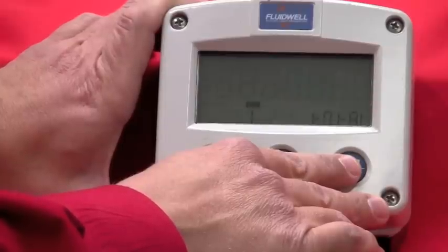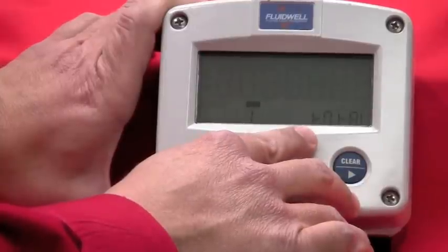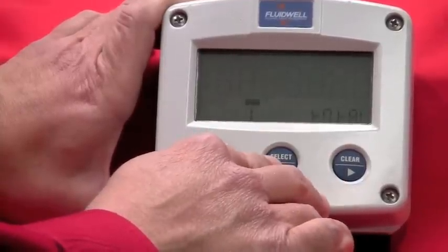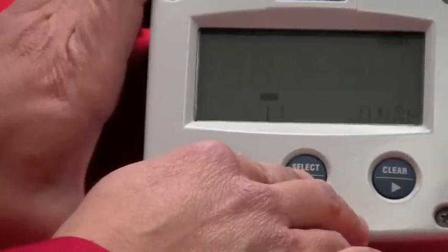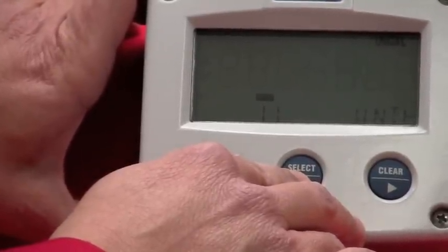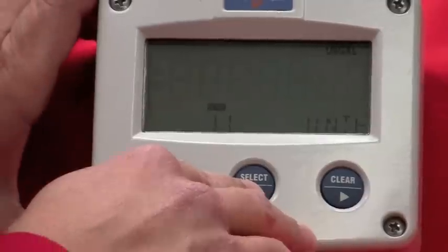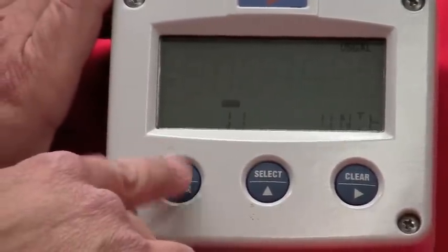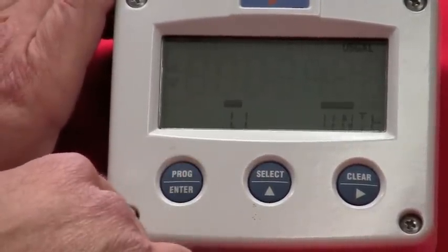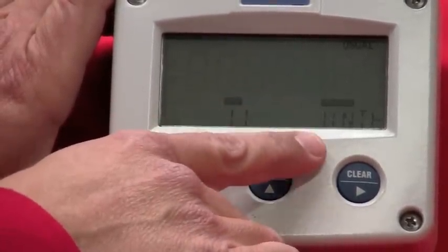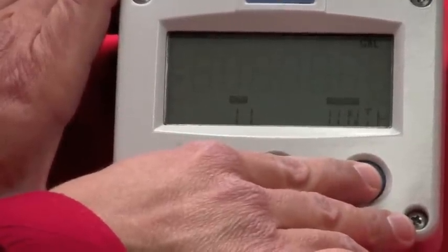To set the meter up and configure it, to drop into any of the main menus here, you're going to utilize your select key. So I'll hit it once. You'll see units. Now to program it or change the units, right now I'm in U.S. gallons. To change that, just push and release the program key. You'll notice now programs is flashing, units, and now I can scroll through the various units here.